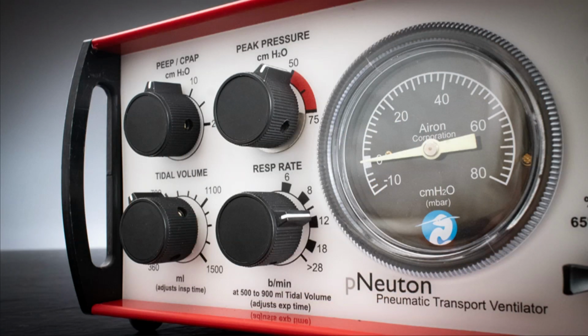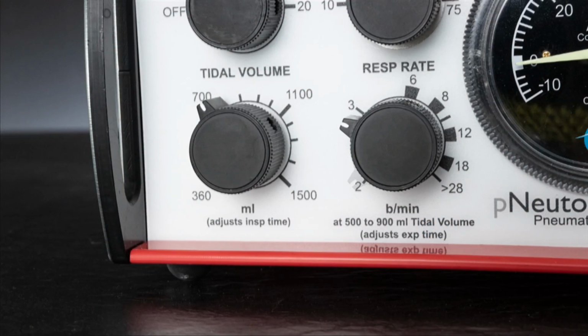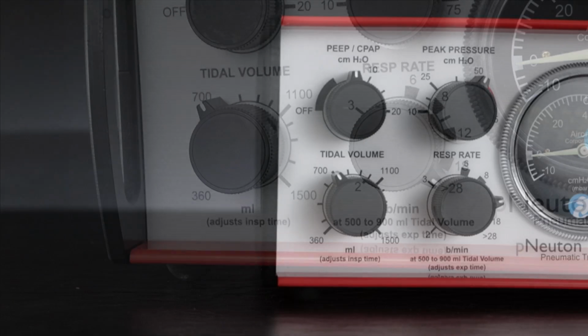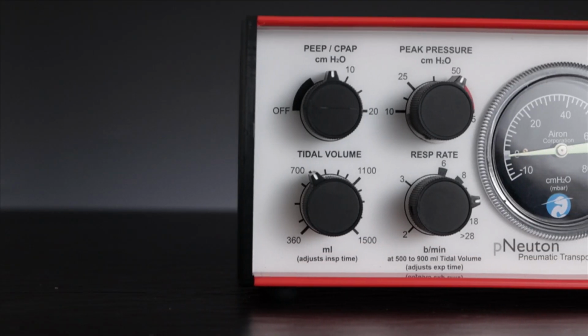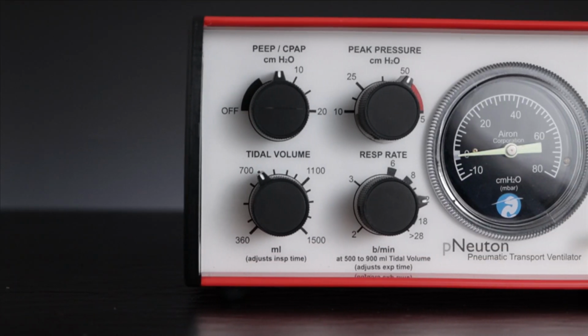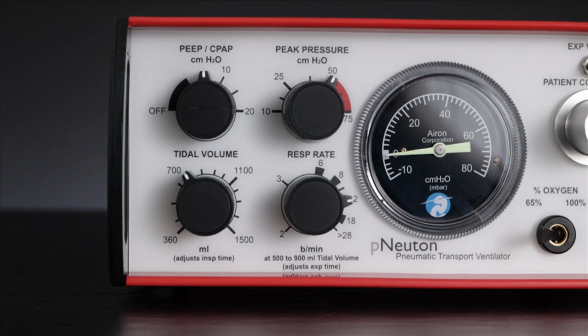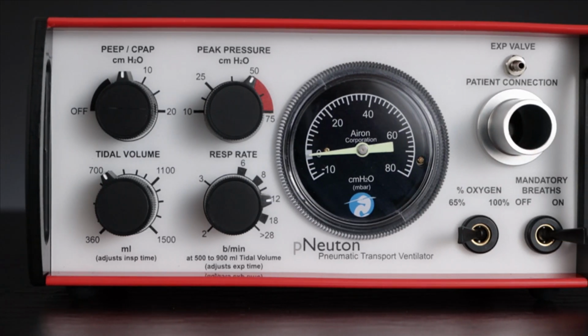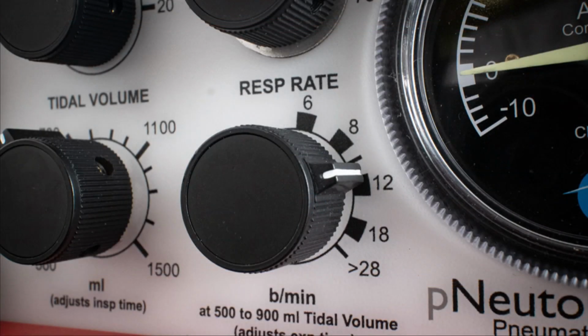Respiratory rate control. To the direct right of tidal volume is the respiratory or resp rate control. It accommodates a patient mandatory breath rate in a range of 2 to greater than 28 breaths per minute. There is a wide range setting at lower respiratory rates to provide better control for slower intermittent mandatory ventilation, or IMV rates.